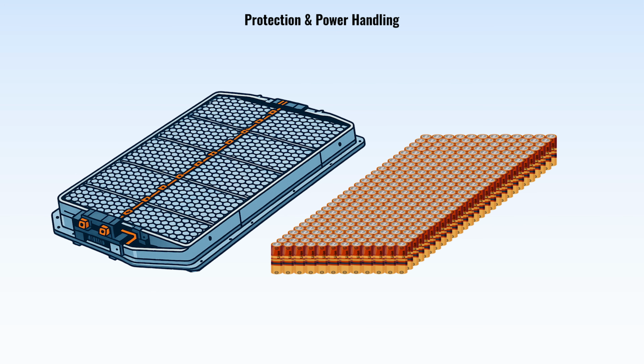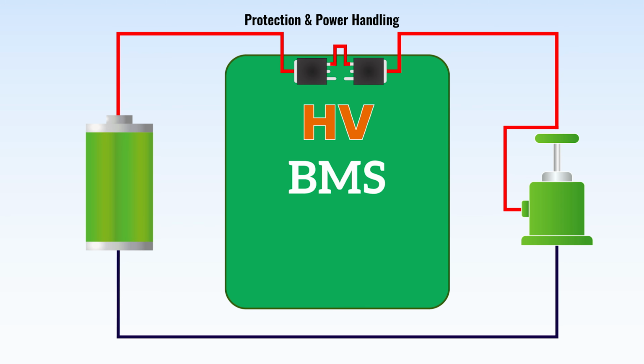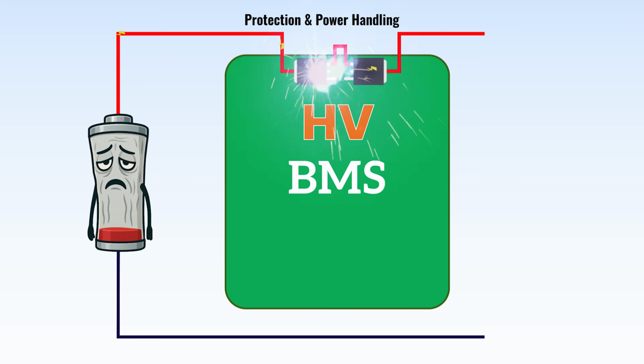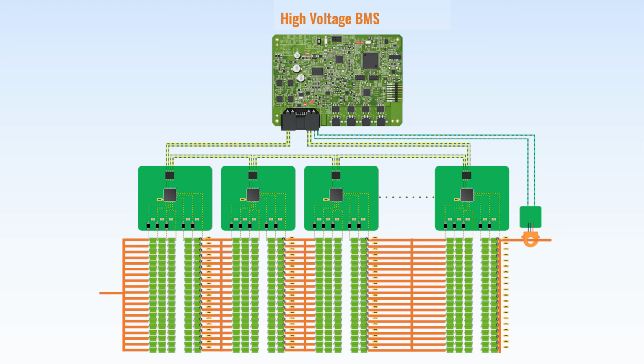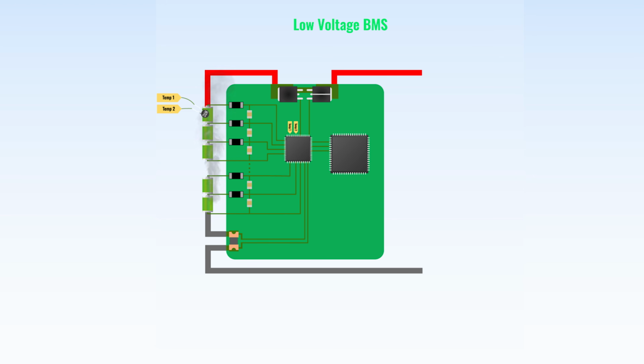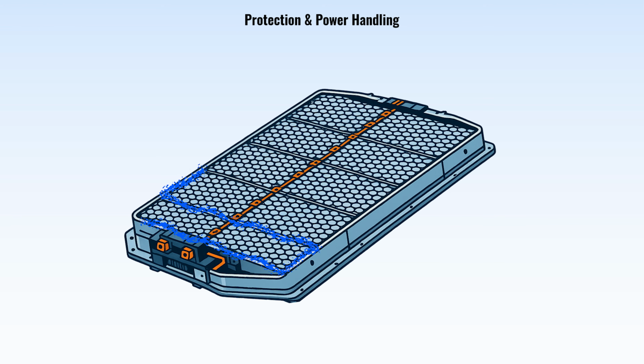An HVBMS manages a pack that can dump huge power, so it has more robust protection mechanisms. Both high voltage and low voltage BMS will do over voltage, under voltage, and over current protection — the difference is how far they can go. For example, a high voltage BMS often adds more advanced thermal management integration. Thermal management in a small pack might just be a temperature sensor to stop charging if it's too hot, whereas an HVBMS might actively manage a cooling system for the battery.